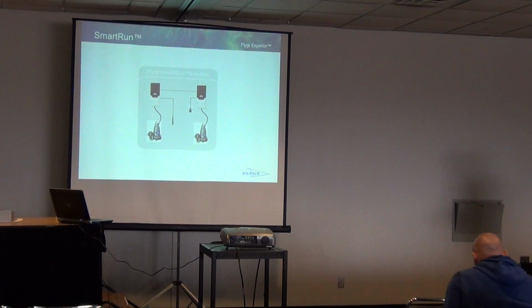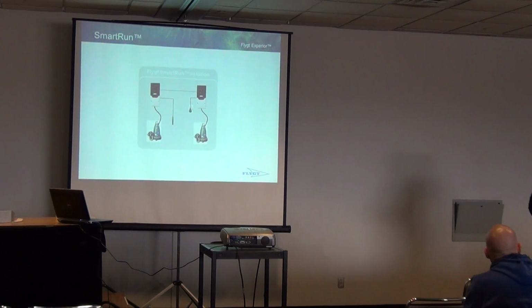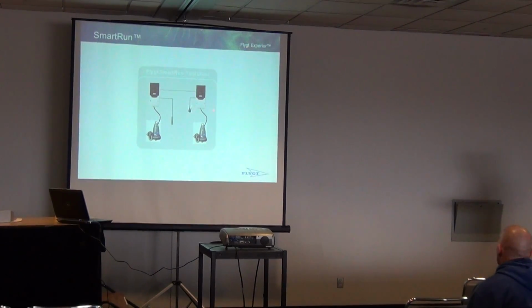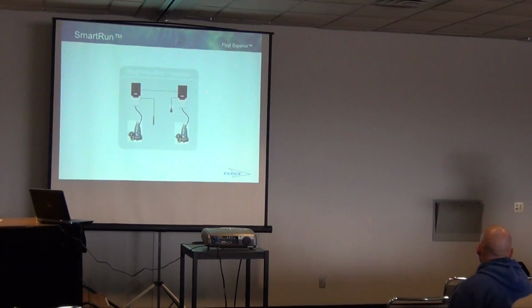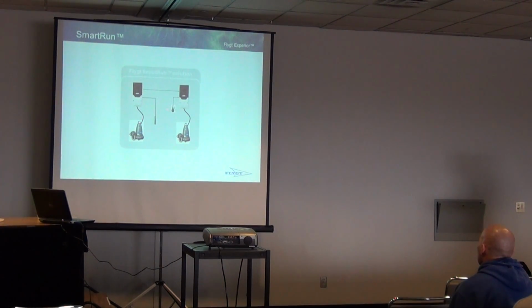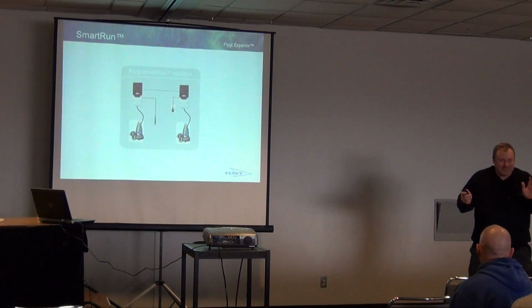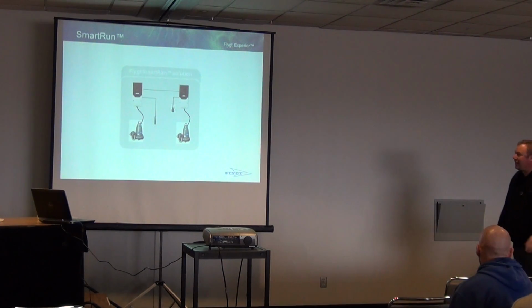We are very used to running our pump stations in an alternation sequence, okay? This is a new concept in which each one of these controllers is assigned to one pump. And each pump, to make it simplistic, has its own brain. The only thing that it shares is a high-level float for a high-level emergency, and a transducer signal that they both share where the level is in the station. Other than that, they're independent on their starts and stops and all that with the set points. And I'll talk about that a little more because everybody is looking at me with this blank stare. But what does that really mean?